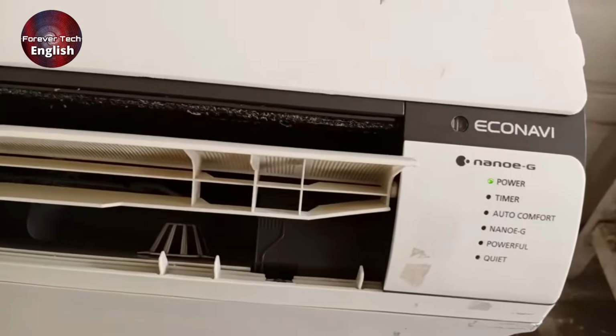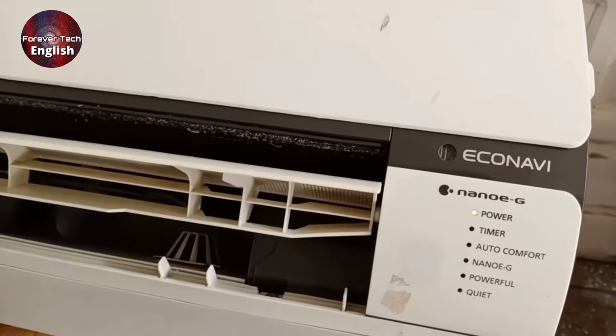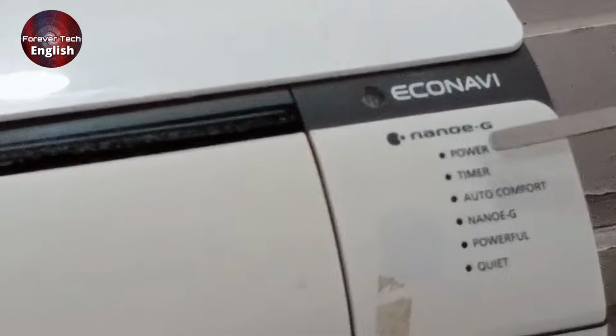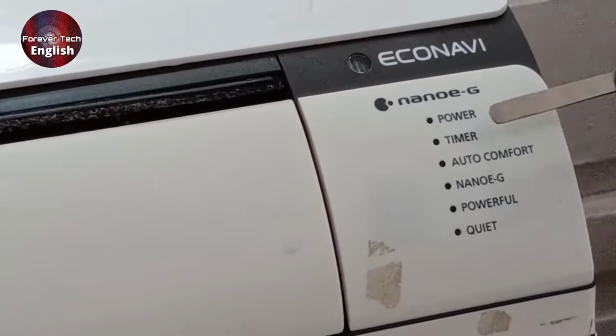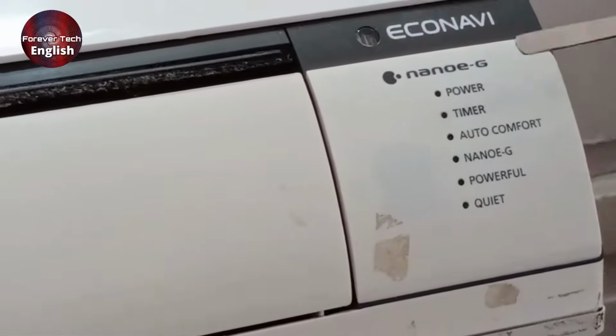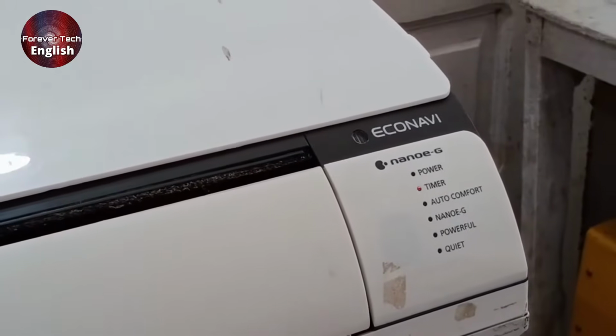This is a Panasonic mini-split air conditioner indoor unit. The error code has appeared on the display, and you can see the timer light is blinking. This indicates there is an error. We will check this error code using the remote. I will now find out the error code using the remote.